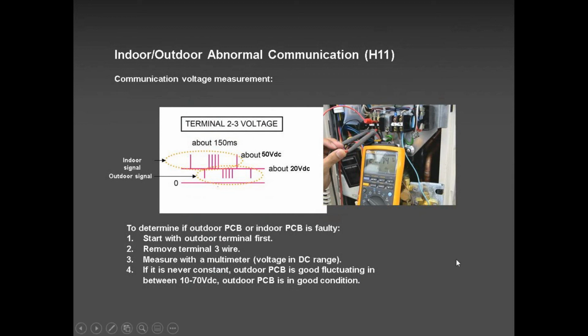Okay? So now let's talk about troubleshooting. Now this troubleshooting is applicable to all the Panasonic models that we are selling in the US, whether it's a single zone or a multi-zone. This troubleshooting guide is the same. So let's say H11. H11 applies to both multi or single. And what is H11? H11 is a very common error. And in most cases, during brand new installation, I found out cross wires are causing H11.